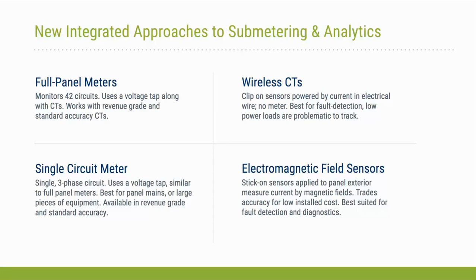The single circuit meter is another technology. This is for metering single 3-phase loads. It uses a voltage tap, similar to full panel meters in that sense. However, as you can imagine, we need a meter for every single breaker or 3-phase load we have, so it wouldn't be an ideal scenario for fully monitoring a 42 breaker panel. They definitely provide high accuracy results, and come in revenue grade or standard accuracy.